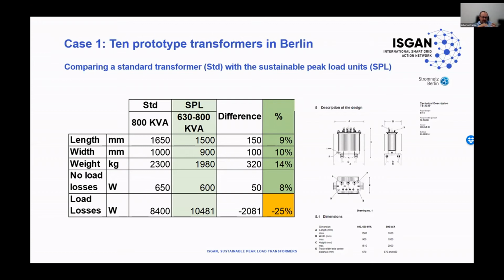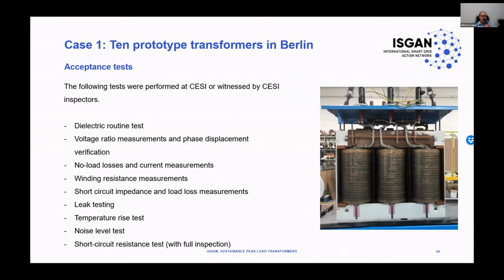But if we go to the next slide, the reason this project is so interesting for us as an OEM is that we did several tests on this project. We performed several different customizations for the project to meet the requirements of the utility and of the technicians of the utility who wanted to test this type of technology. First of all, we produced a transformer respecting 100% the technical specification provided by Vattenfall, and we performed all the type tests, routine tests, and special tests usually requested by the utility, as for example the temperature rise test at the SPL power, checking that the overtemperature of the transformer respects the IEC 60076-14 norm limits.